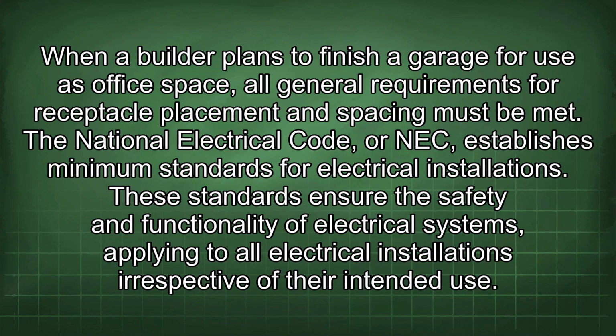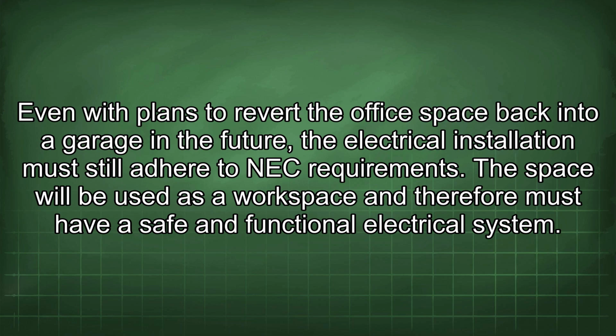When a builder plans to finish a garage for use as office space, all general requirements for receptacle placement and spacing must be met. The National Electrical Code, or NEC, establishes minimum standards for electrical installations. These standards ensure the safety and functionality of electrical systems, applying to all electrical installations irrespective of their intended use. Even with plans to revert the office space back into a garage in the future, the electrical installation must still adhere to NEC requirements.